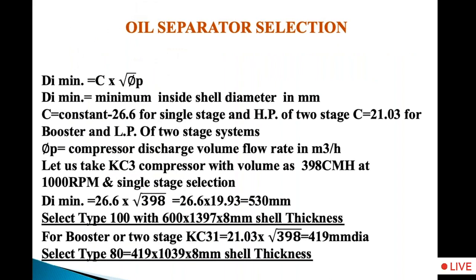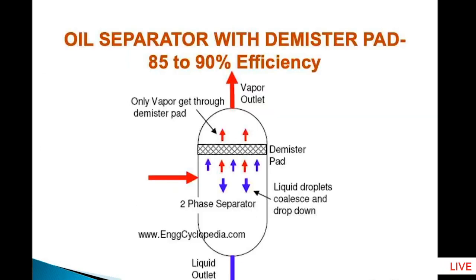This slide shows how to calculate the oil separator diameter and the length. But these calculations I am not reading now for the paucity of time. These will be available to all of you. You can calculate your own sizes of the oil separator. The second oil separator, which is more efficient, is, if you see, there is a demister pad inside the oil separator.